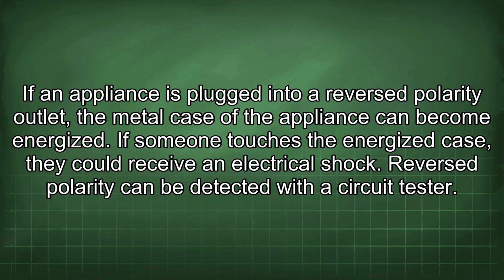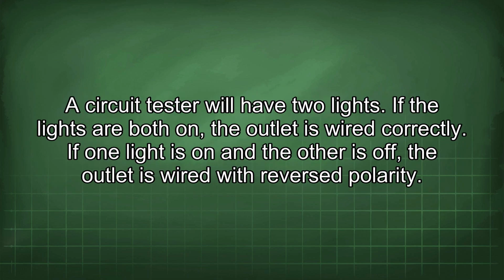Reverse polarity can be detected with a circuit tester. A circuit tester will have two lights. If the lights are both on, the outlet is wired correctly. If one light is on and the other is off, the outlet is wired with reverse polarity.